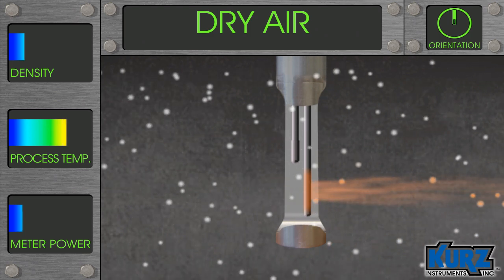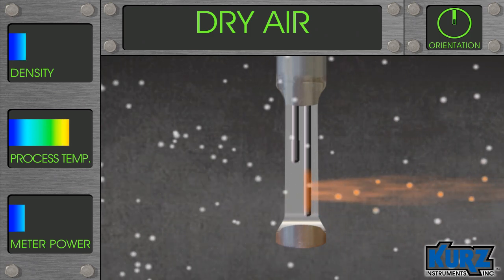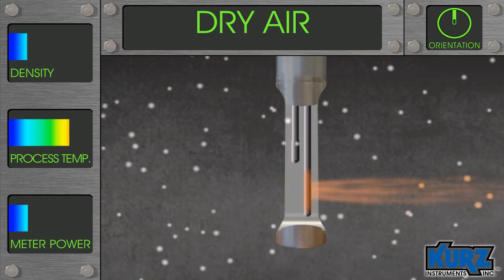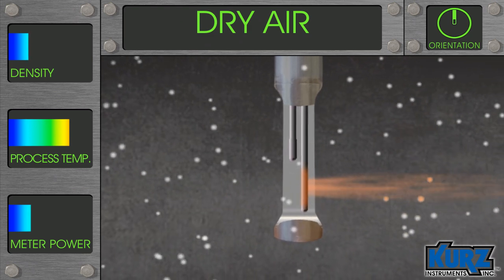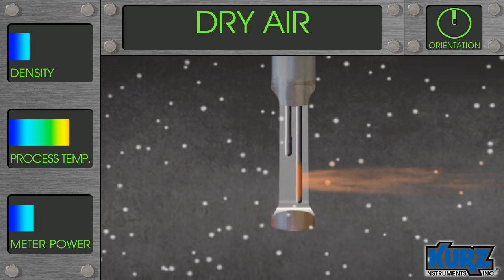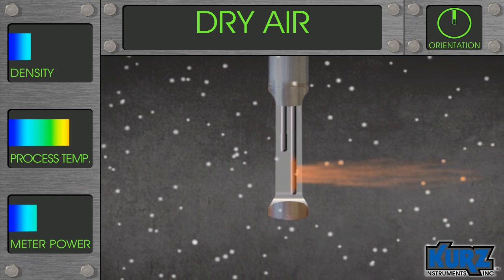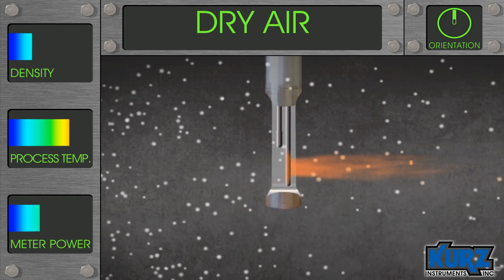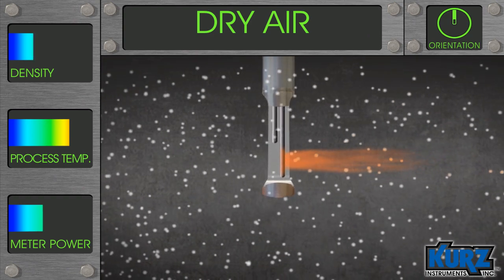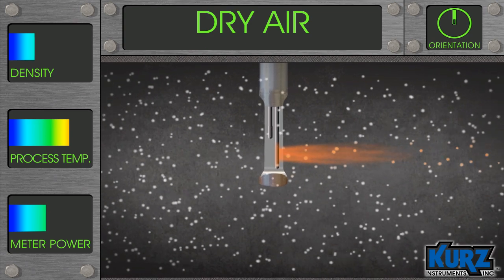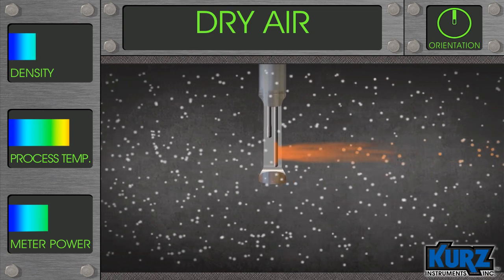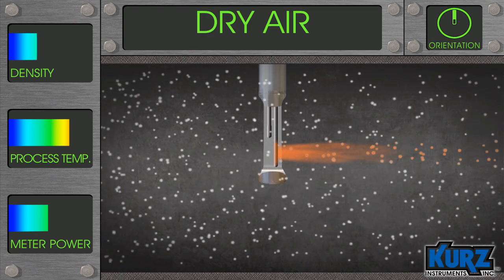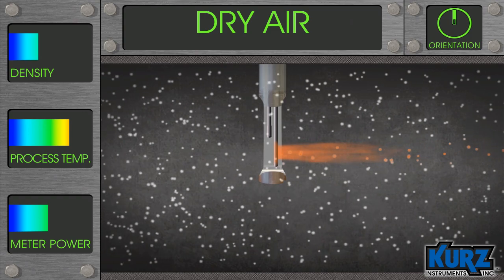Gas molecules strike the heated sensor and draw away heat. To compensate for the heat loss, additional power is directed to the heated sensor to keep the constant temperature differential. The speed of the flow and the type of gas determines the amount of energy sent to the sensor. The amount of energy used to maintain the differential temperature reflects the mass flow rate.